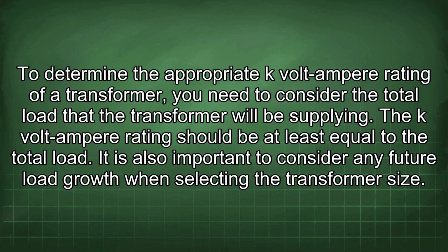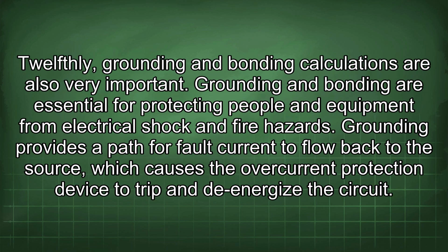To determine the appropriate kVA rating of a transformer, you need to consider the total load that the transformer will be supplying. The kVA rating should be at least equal to the total load. It is also important to consider any future load growth when selecting the transformer size. 12thly, grounding and bonding calculations are also very important. Grounding and bonding are essential for protecting people and equipment from electrical shock and fire hazards. Grounding provides a path for fault current to flow back to the source, which causes the overcurrent protection device to trip and de-energize the circuit.